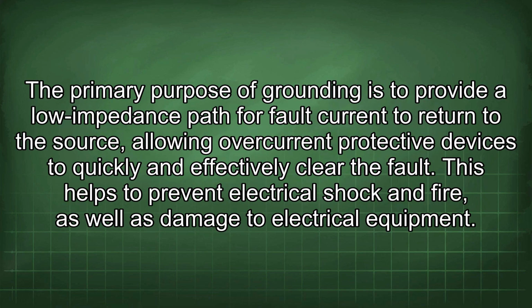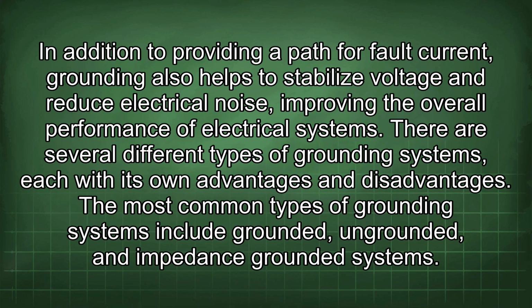The primary purpose of grounding is to provide a low impedance path for fault current to return to the source, allowing overcurrent protective devices to quickly and effectively clear the fault. This helps to prevent electrical shock and fire, as well as damage to electrical equipment. In addition to providing a path for fault current, grounding also helps to stabilize voltage and reduce electrical noise, improving the overall performance of electrical systems.